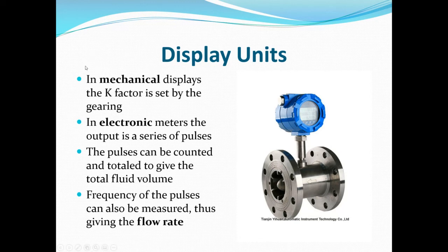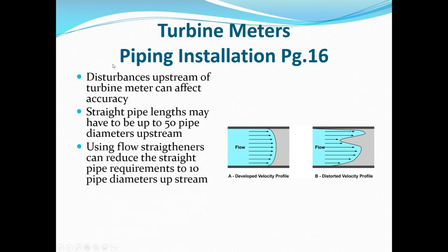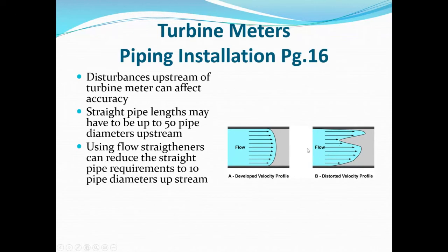Piping and installation considerations: we want a fully developed flow profile, achieved naturally or using straightening vanes or flow conditioning. Disturbances upstream can affect accuracy. Straight pipe lengths may need to be up to 50 diameters upstream. Using flow straighteners can reduce this requirement down to 10 diameters upstream. That's why the construction generally includes engineering design to straighten out that flow.